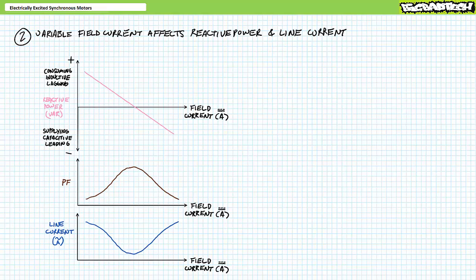You'll recall that squirrel cage induction motors necessitate the constant consumption of positive reactive power necessary to power the rotating magnetic field and drive the process of induction central to their operation. Electrically excited synchronous motors, in contrast, don't operate using induction but rather have two independent interacting magnetic fields. If the rotor field is weak, the stator needs to draw reactive power, as would a squirrel cage induction motor. If, however, the rotor field increases in strength, the stator doesn't need to consume as much reactive power, thus line current decreases and power factor increases. Additionally, one can overexcite the rotor so much that the stator appears to be capacitive in nature and supplies reactive power. This can be used to power factor correct other loads, as we'll examine in the upcoming synchronous condensers lectures.